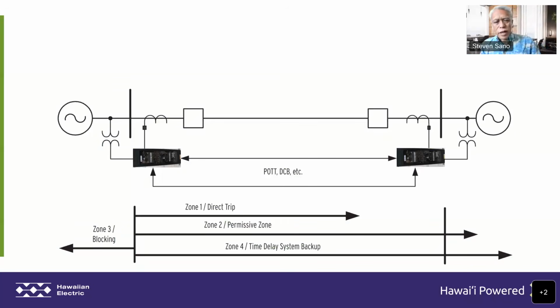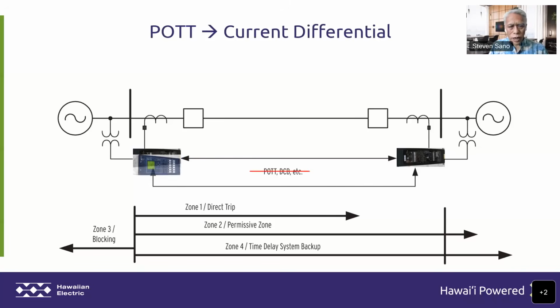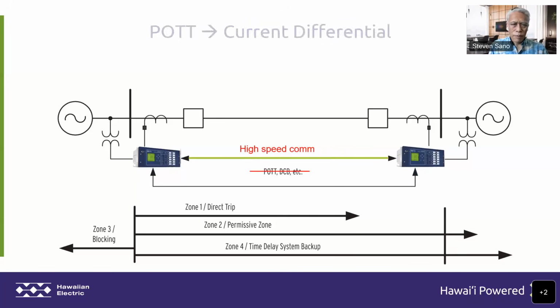These next couple of slides are just illustrations of what these changes could look like. This simple diagram is meant to show a transmission line, the 2 breakers on the end of the line, and the 2 relays connecting them. As I mentioned, we have our POTT as our standard, which we're slowly changing out. So POTT, if it becomes insufficient, we'll change that out to current differential by changing out the relays and possibly the communication.